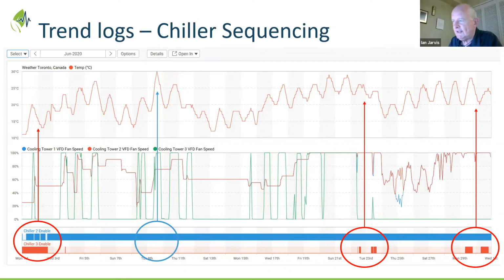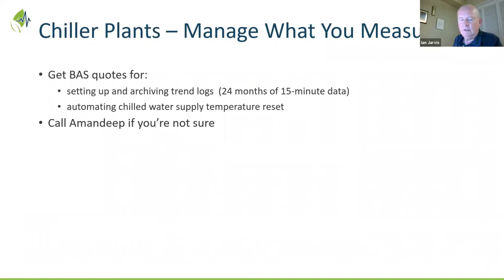The other thing you're showing me is cooling tower 3, the green one at the bottom there, regularly goes up to 100% fan speed, and that's the most inefficient that a variable frequency drive can be. So better control of the cooling towers would also help a bit with it. Definitely. And another thing you notice, especially at the third circle, is you can see the chiller came on because there was a drop in the cooling tower speed, or there was a switchover between the 2 cooling towers. That maybe resulted in a supply water temperature increase in the chiller and brought on the chiller for only 20 or 30 minutes, and then it went off. So you don't need 2 chillers running at that time, and you can get away with 1 chiller.